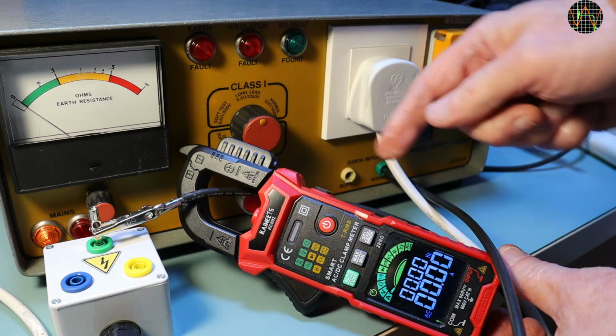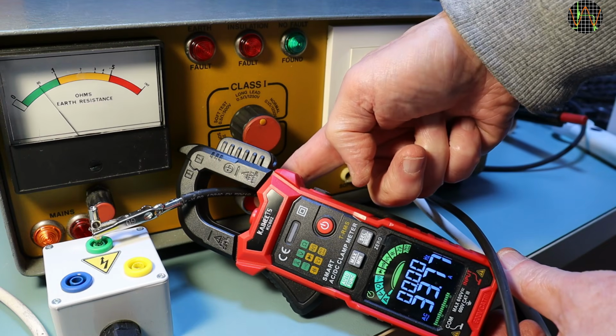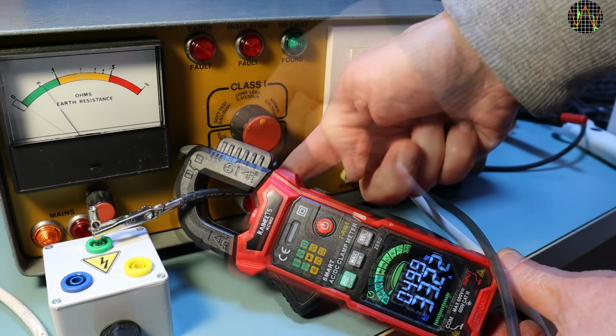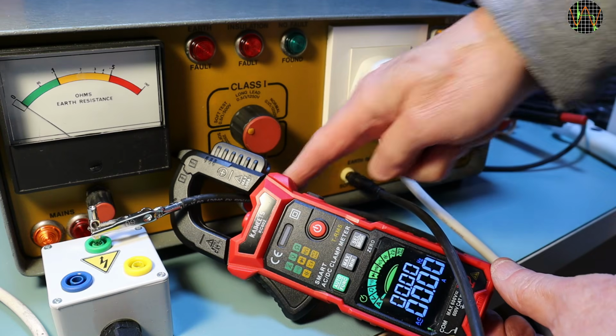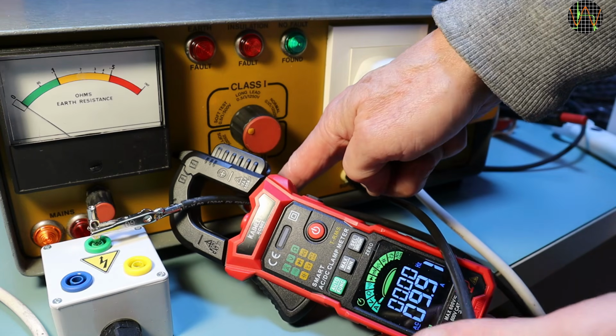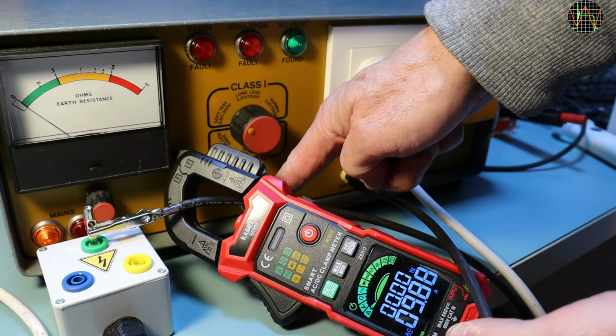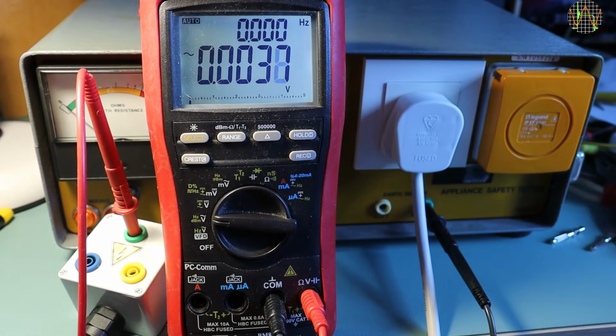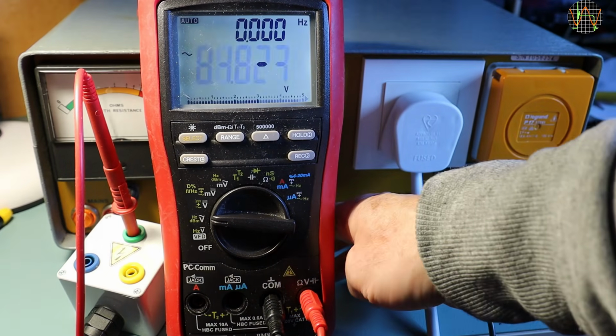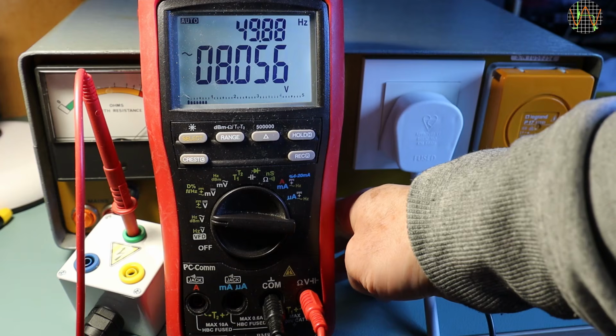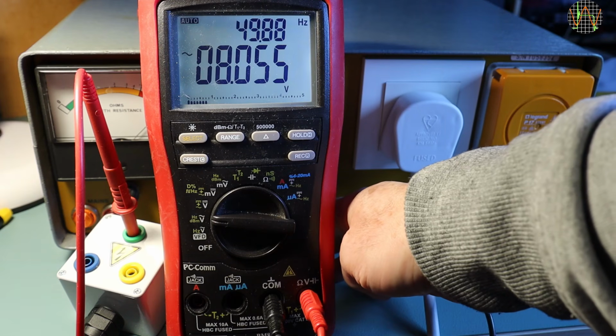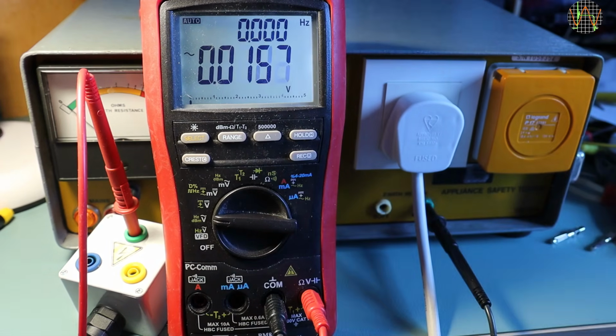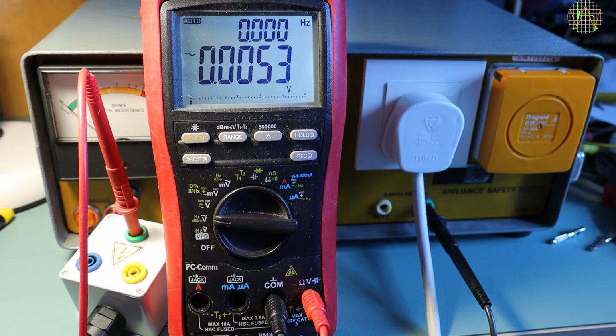The current flows as long as I keep the button pressed. How about the long lead setting? It's the same, 33 amps, no difference. And for the soft setting? Only 10 amps. That's really soft compared to the others. But the voltage used for the earth resistance measurement is actually quite small, just 8 volts AC. Okay, that was the earth resistance part of the class 1 tests.